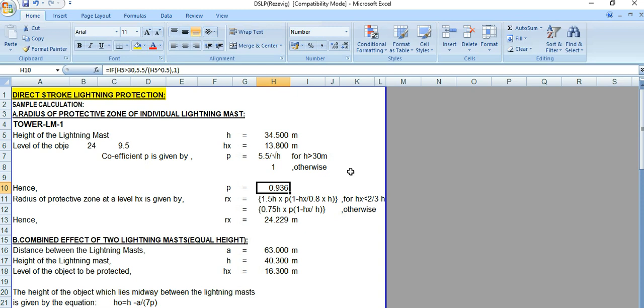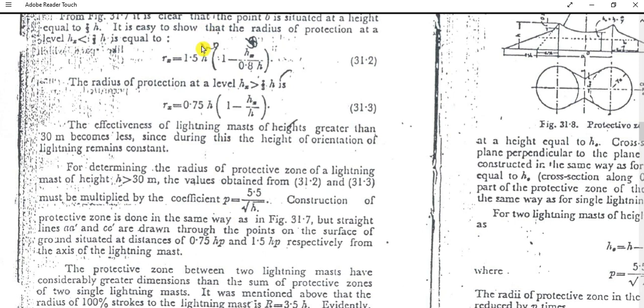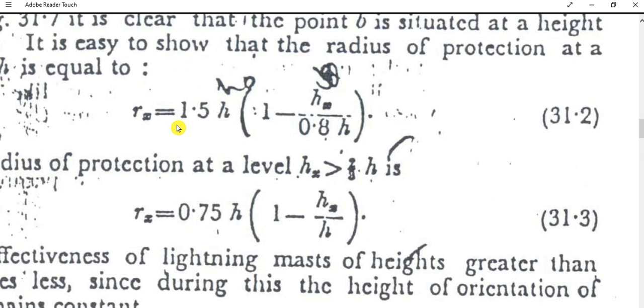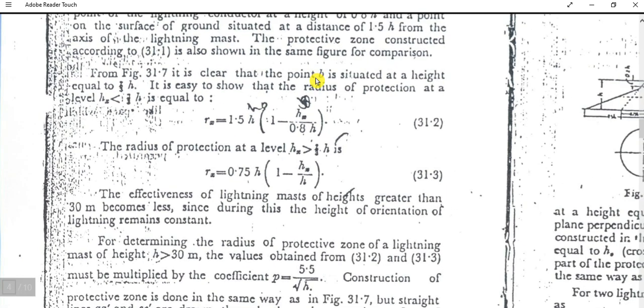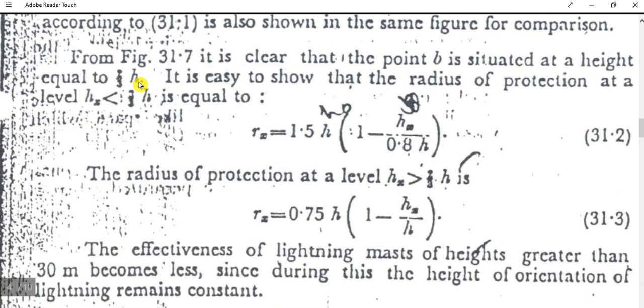The radius of the protective zone at level hx is given by: rx = 1.5h × p × (1 − hx / (0.8h)), applicable when hx is less than two-thirds of h. Otherwise, the formula is rx = 0.75h × p × (1 − hx / h). Let's check where these formulas come from in the reference — here you can see both cases defined based on the condition on hx relative to h.